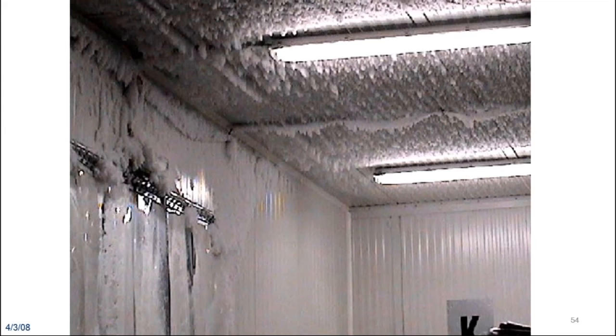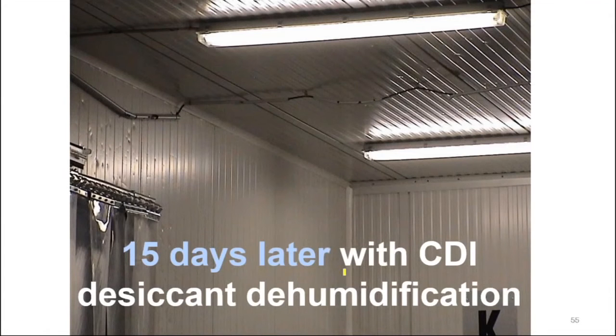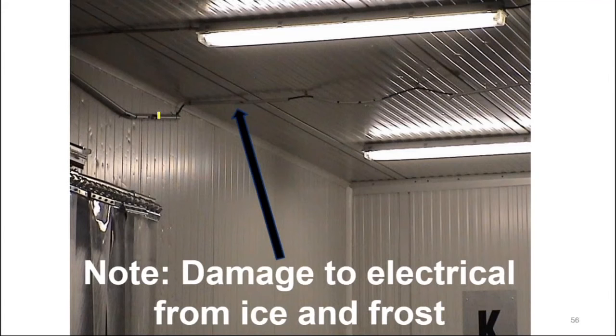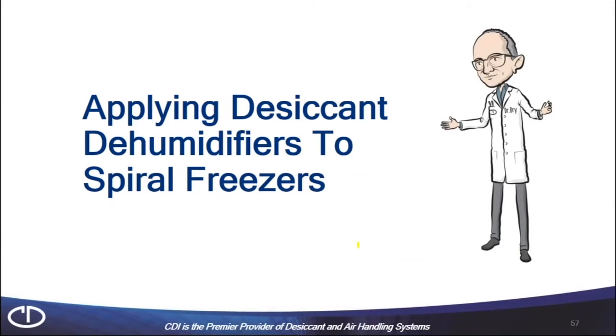Stalactites and stalagmites and all kinds of ice hanging around. Well, after 15 days of a CDI unit, it even exposed, look at this, the damage that happened to this electrical conduit up here, just totally ripped up from that ice that had been building up and defrosting over the years. So now, with the addition of the desiccant unit, that room is dry.